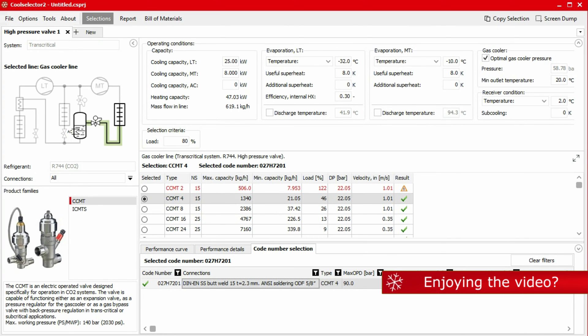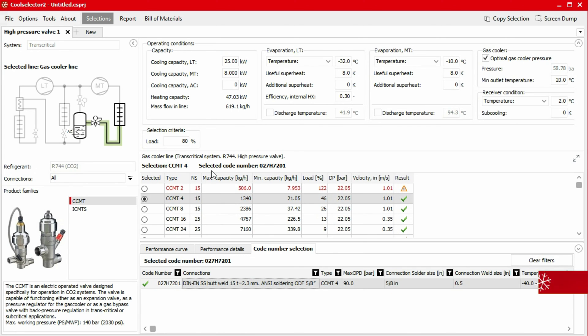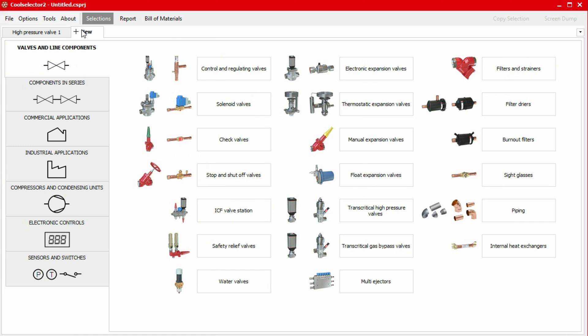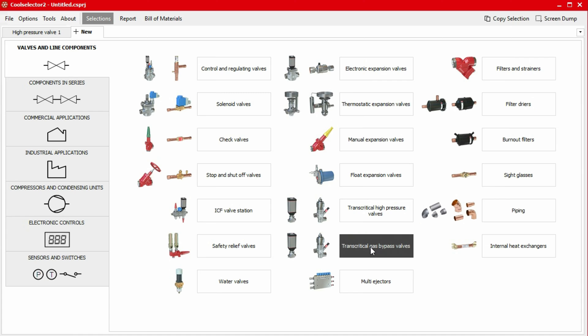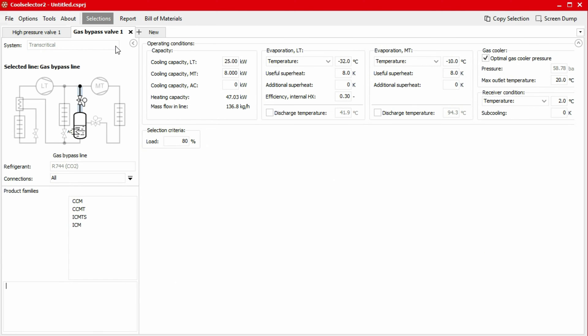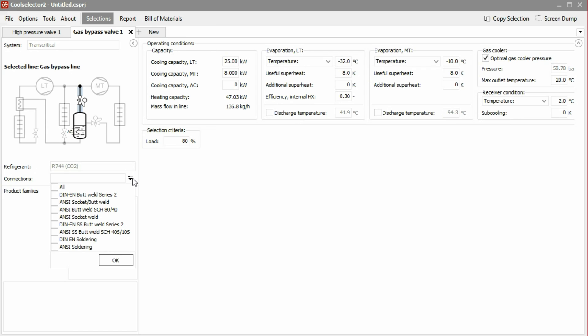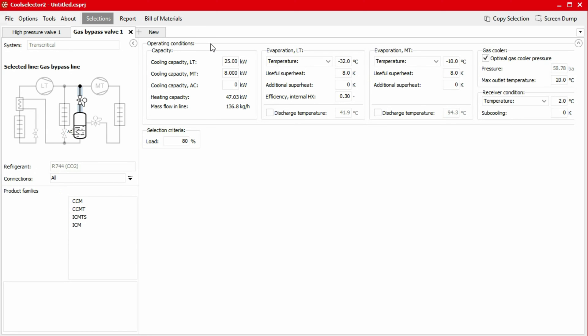We start the selection process for a transcritical gas bypass valve for our system with the same operating conditions as our previous example by opening a new tab, then clicking on the valves and line components tab, and then selecting the transcritical gas bypass valves option. Similar to the previous case, in the left-hand panel we see that the system type is defaulted to transcritical. The line where the valve will be installed in the system is highlighted and the refrigerant has been pre-selected as CO2. You can notice that CoolSelector 2 keeps the operating conditions from our previous selection. This option is useful when we want to select multiple components in different lines or compare different components in the same location for our system.